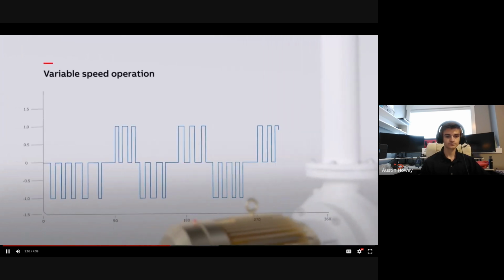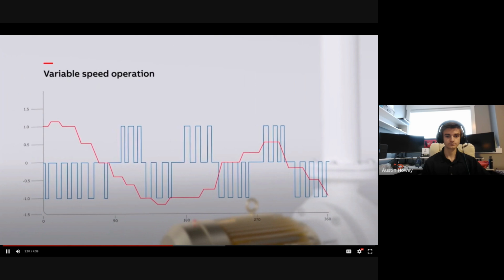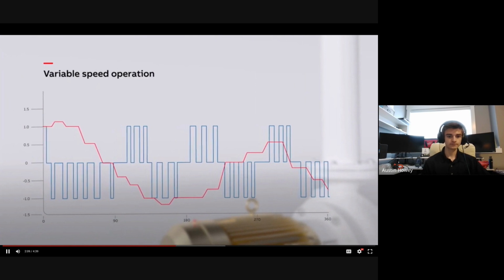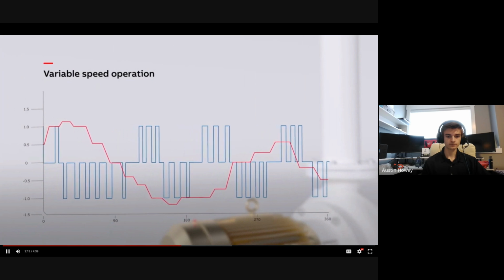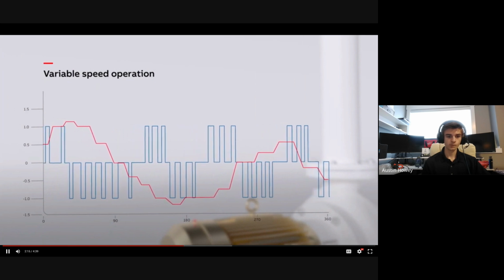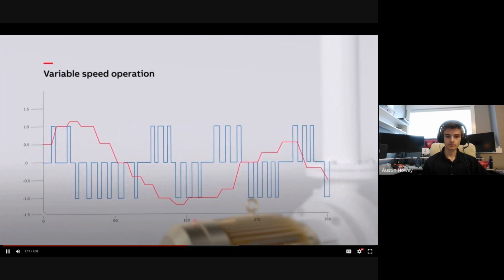When motors are controlled by a VFD, the power is converted to a series of high-frequency pulses that emulate the approximate sine wave, but is not exact, with high harmonics. The result is an imbalance known as common mode voltage.